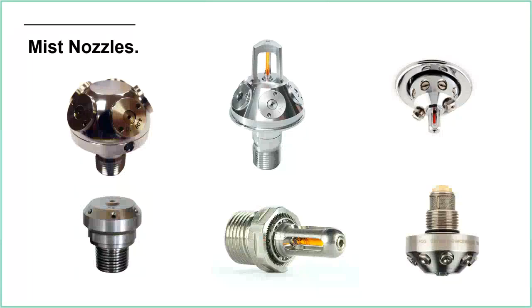The point is they're not activated individually, they're activated via some other system. It could be a manual push button, or a smoke detector, or something that's going to detect a fire in the room, and then it will activate all of the nozzles within that room. But the main point is that in a sprinkler head the droplets are created by hitting the deflector plate. In a mist nozzle, they're created by forcing the water through a small hole or small orifice.